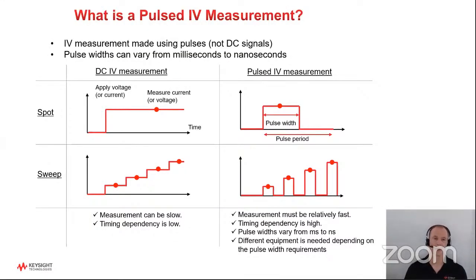So just a review real quick here. What is a pulse? What do I mean by a pulsed IV measurement? Again, in a pulsed IV measurement, we're using pulses, not DC signal levels, obviously. The important point is that pulses can actually vary quite a bit. You can have pulses that are milliseconds, or you can also have pulses that are down to nanoseconds. Now, nanoseconds is where you're really talking about ultra fast measurements.